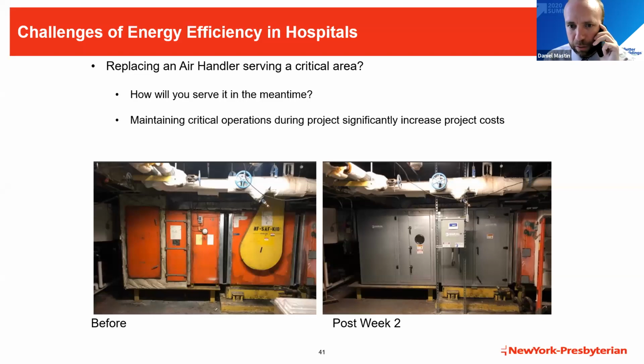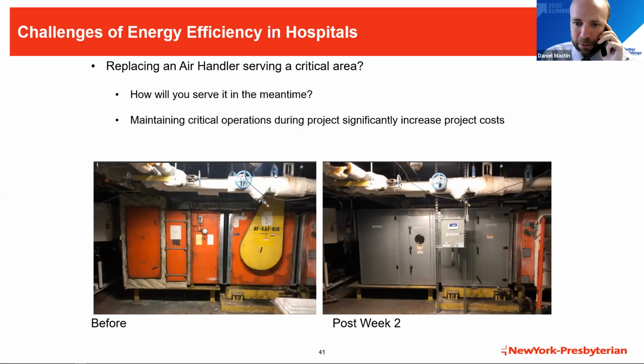Another way to do it, pictured here, is we demolish and replace one section of an air handler at a time over the course of three weekends. Friday, the space gets shut down. We demolish one section, replace it, and start it up as a Frankenstein unit, operating it for the week. The next week we might demolish the coils, replace that section, start it back up, running a mix of the old and new unit. The third weekend we replace the mixed air section, demolish it, and then we have a brand new unit. We're running around the clock with demolition and construction from Friday evening till Monday morning to get it back in operation for the Monday through Friday work week. Paying premium time, it's costly to do a project like that.